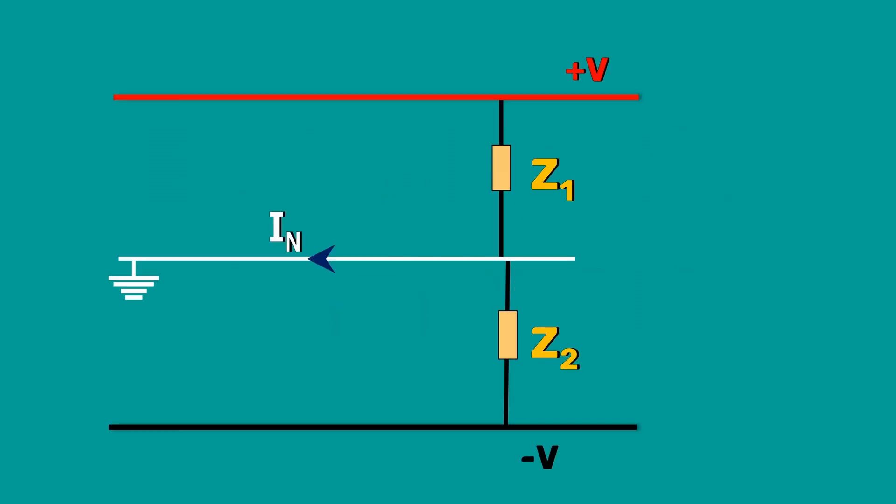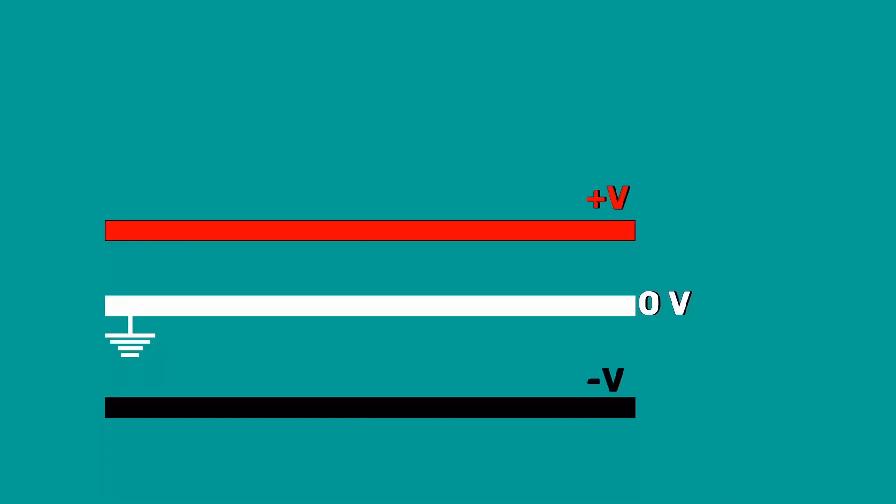If the loads on both sides of the neutral are not equal, then an out-of-balance current will flow in the neutral wire. The magnitude of this current will be very small as the neutral wire carries only this small current. The area of the cross section of the neutral wire is designed to be small compared to the other two.